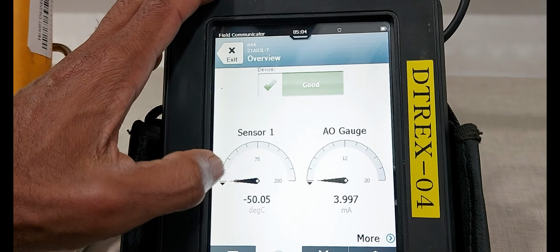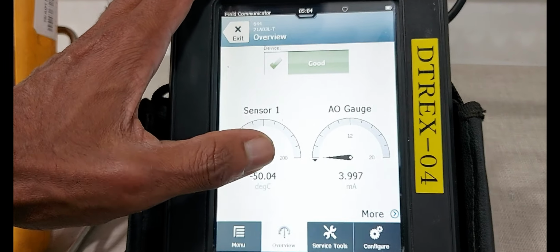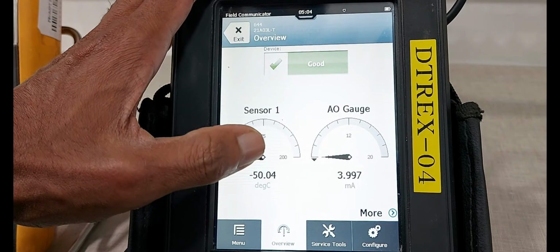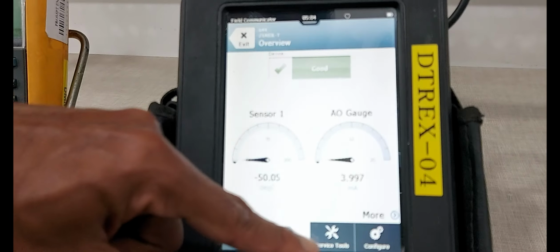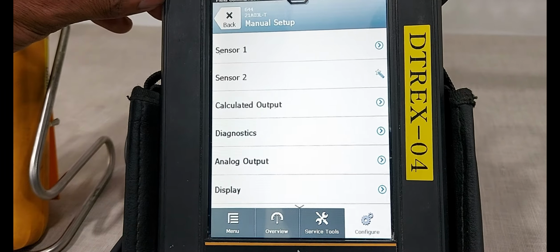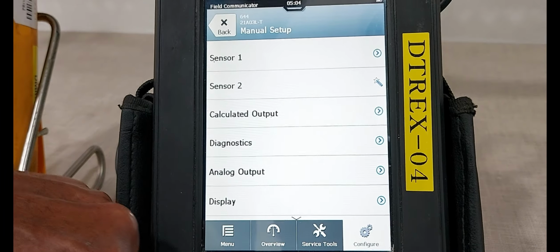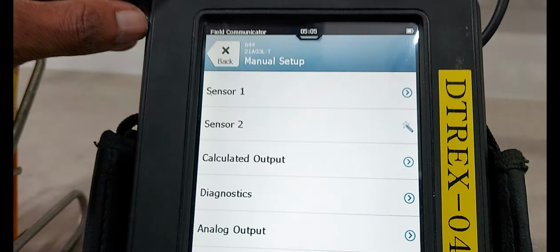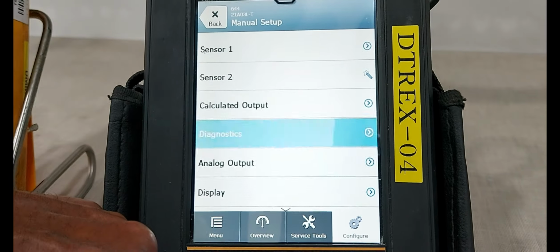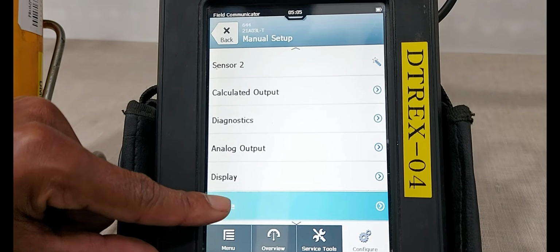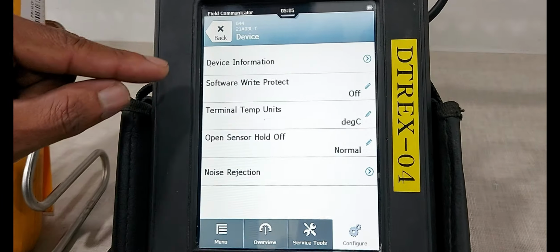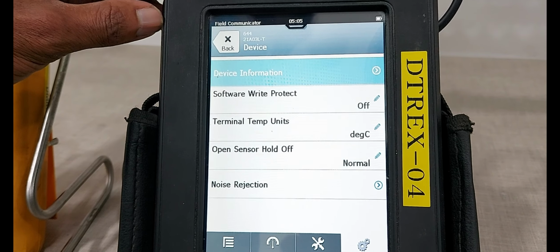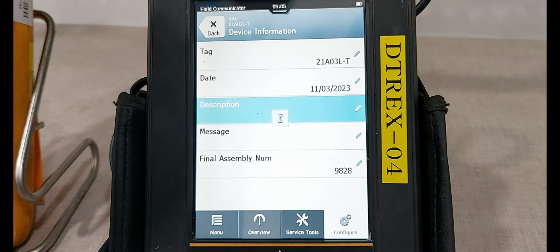Next we are doing the procedure for adding instrument service, description and tag number. First select the configuration menu. Select the manual setup. Move it down. Device information. Tag number already assigned. Next we are assigning the description, instrument service. Okay, we are opening that one.